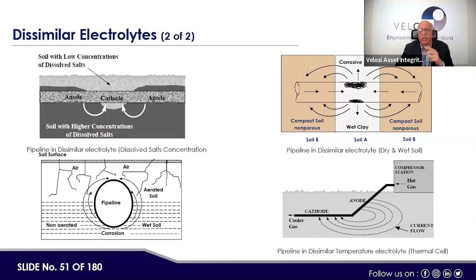For example, if there is a vertical well casing for the anode, the electrolyte from the top to bottom of the anode, when buried in the soil, may have different conformations and different relationships with reference to the resistivity of soil from top to bottom. So we need to assess the optimum resistance and the maximum voltage potential required to maintain electron flow. The well casing is exposed to different electrolyte compositions, and that has to be considered.